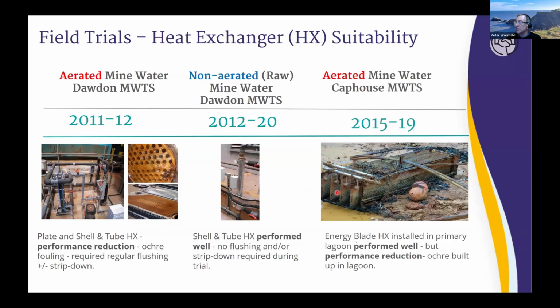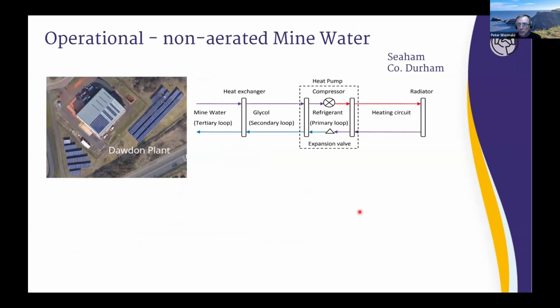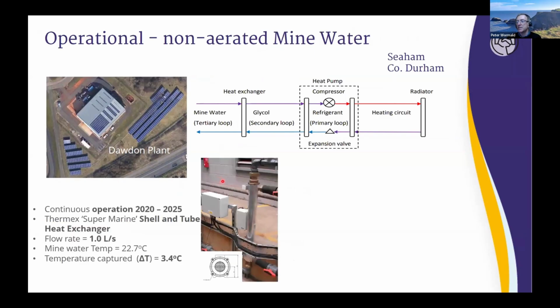Elsewhere, at the Cap House mine water treatment scheme, we trialled energy blade type heat exchangers in our primary lagoon for the treatment centre. They performed well, but there was a reduction in performance due to ochre buildup within the lagoon. We then installed our first operational waste mine water heat scheme at the Dawdon Plant.